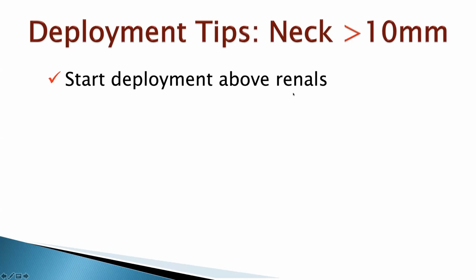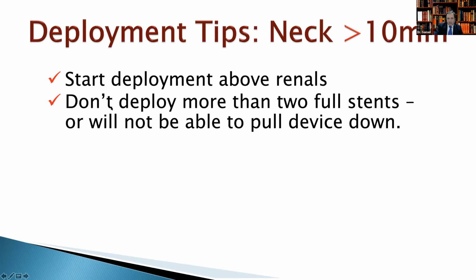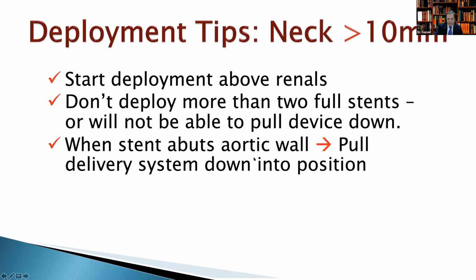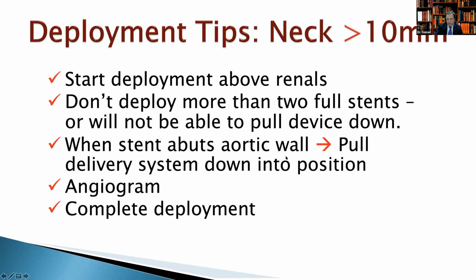So what are some tips if the neck is short, about 10 to 15 millimeters? Always start to deploy it above the renal. This is very important because it's always easier to pull the device down than push it up. Then don't deploy more than 2 full stents, because if you deploy more than 2 full stents, you cannot pull the device down. After that, wait until the stent is up against the aortic wall, and then pull the delivery system down all the way to the position which you want. Do an angiogram, confirm it, and then complete deployment.